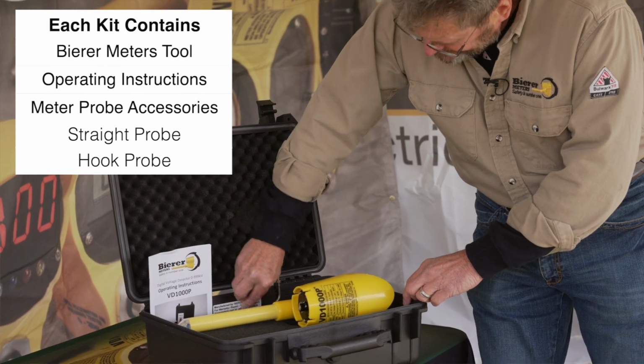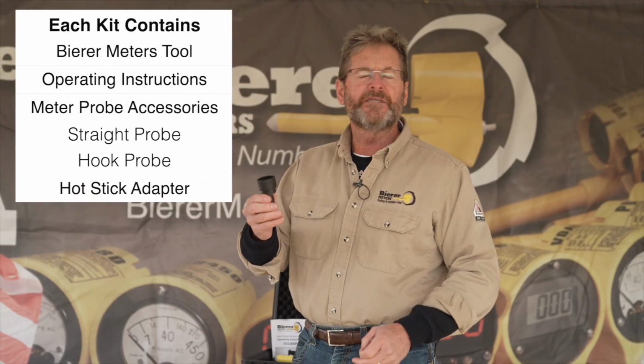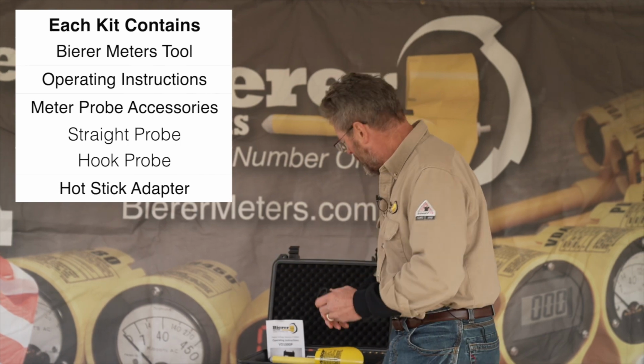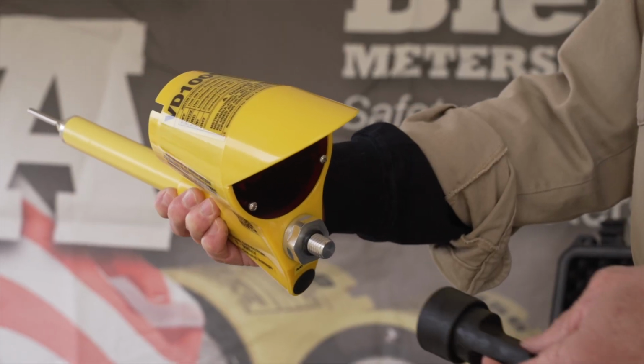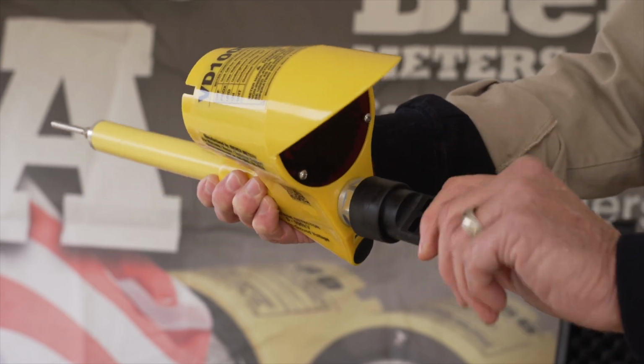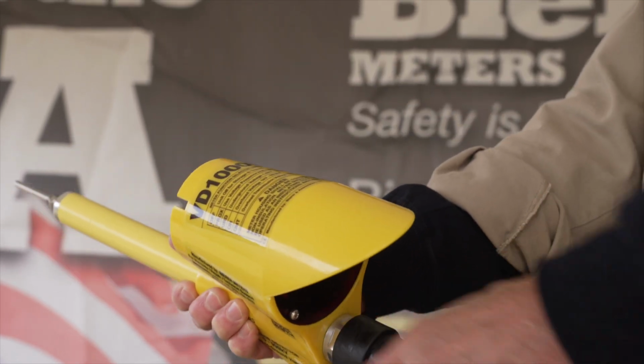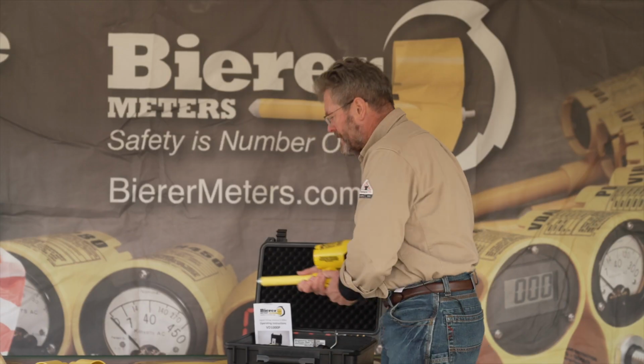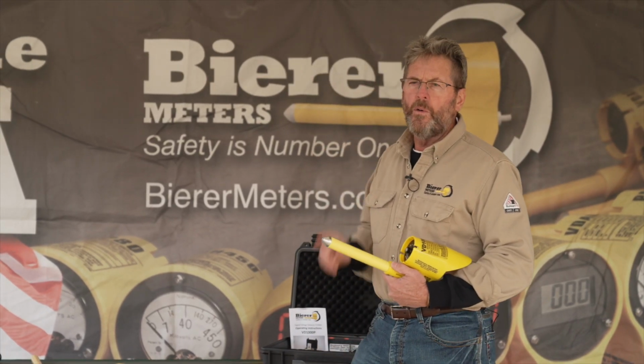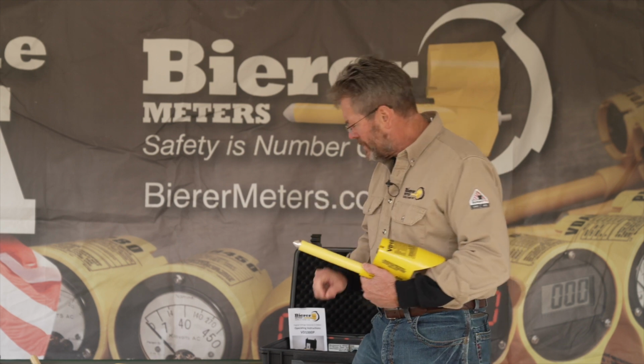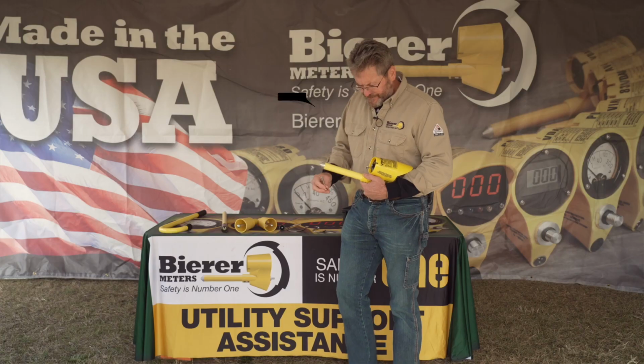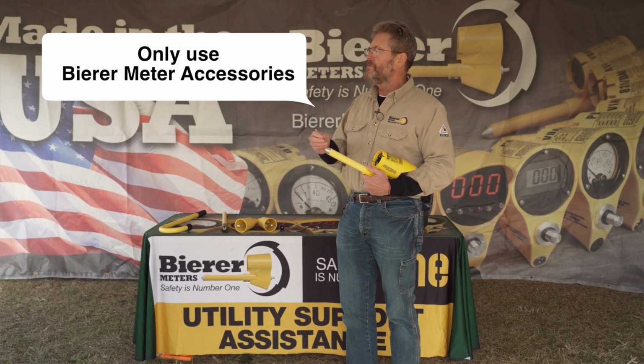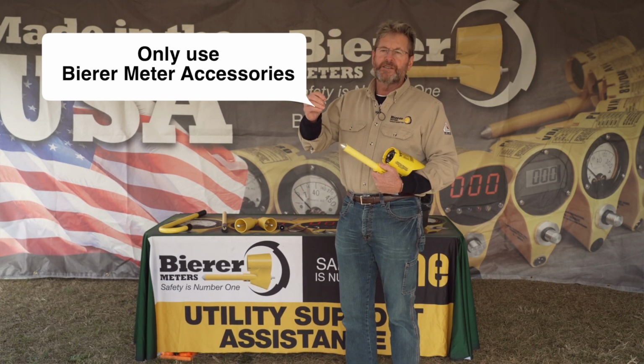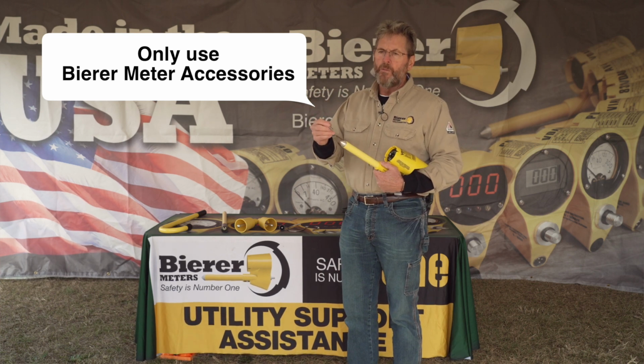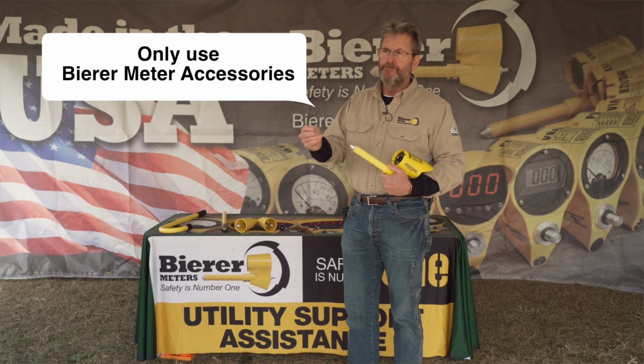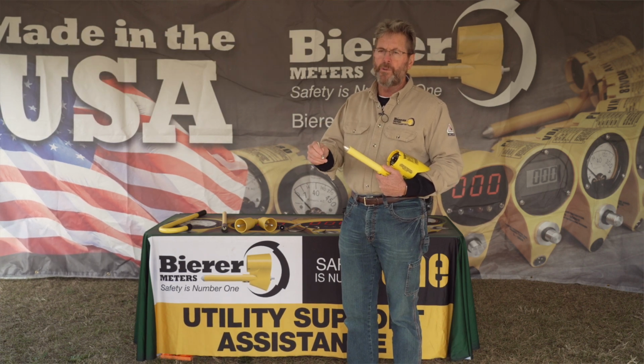You're going to see also in the kit your hot stick adapter, and this goes onto the back of your meter onto the quick change. This is also where you're going to change out your battery for your tool. Now the meter probe accessories are very important, you always want to keep these in use when you're using your tool. And on our devices, you want to make sure you use Bierer Meters meter probe accessories only. Do not interchange them with other manufacturers' meter probe accessories. Always use Bierer Meters products.